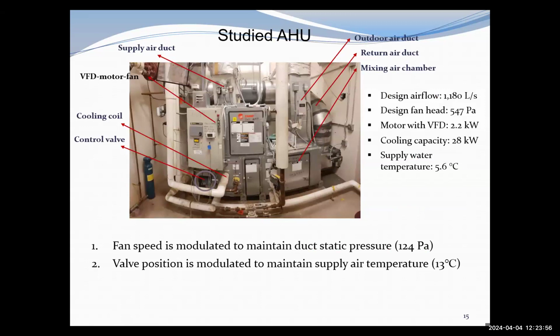So this is our studied air handling unit. This air handling unit is serving the buildings on OU campus. Maybe you can also visit the air handling units there yourself. So this is the outdoor air duct. This is the return air duct. The outdoor air and the return air are mixed in the mixing air chamber here. And then it will go through this cooling coil. This is a cooling coil inside. And here is a control valve to modulate the chilled water flow rate through the cooling coil. And then the cooled air is supplied through this supply fan and delivered to the conditioned space through this supply air duct here.